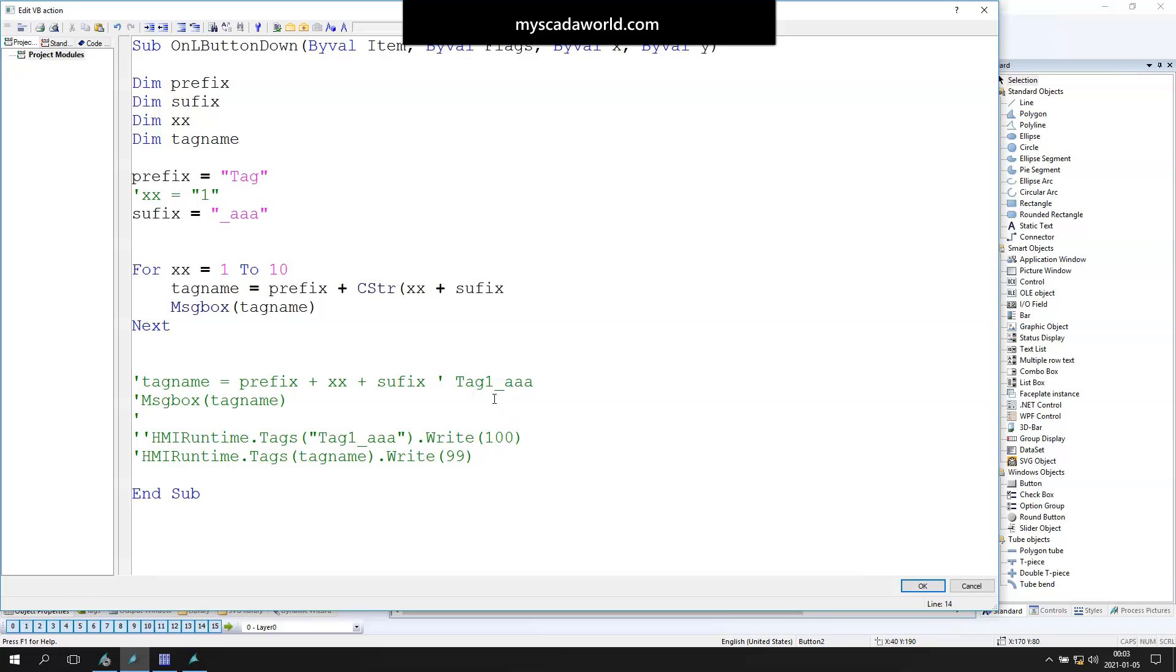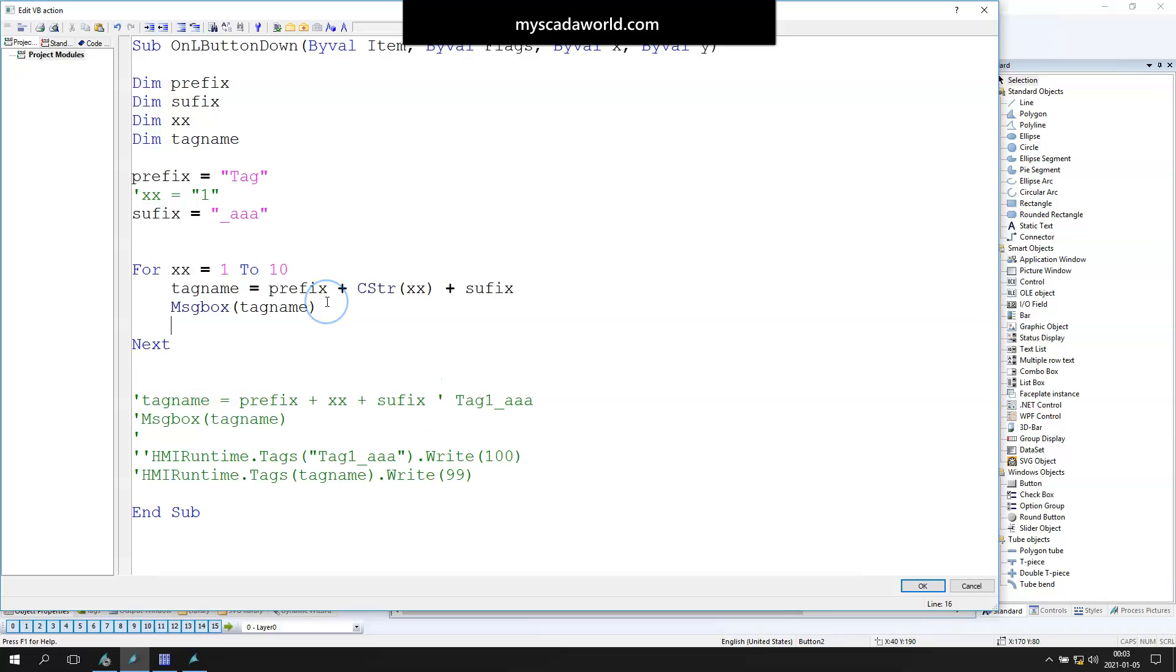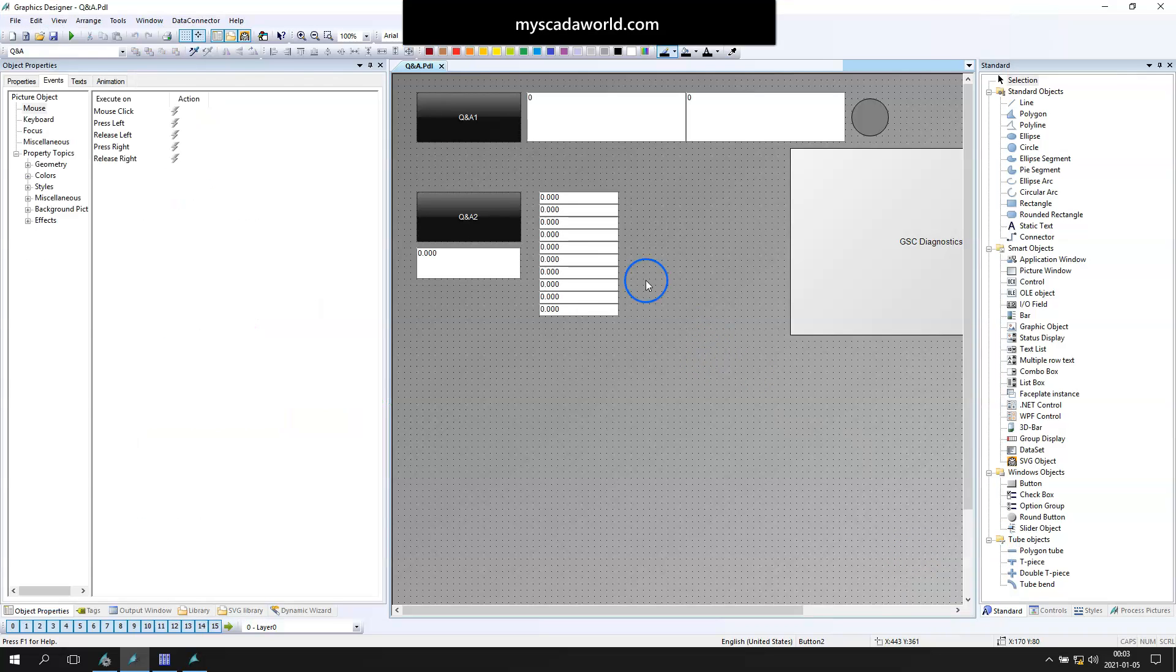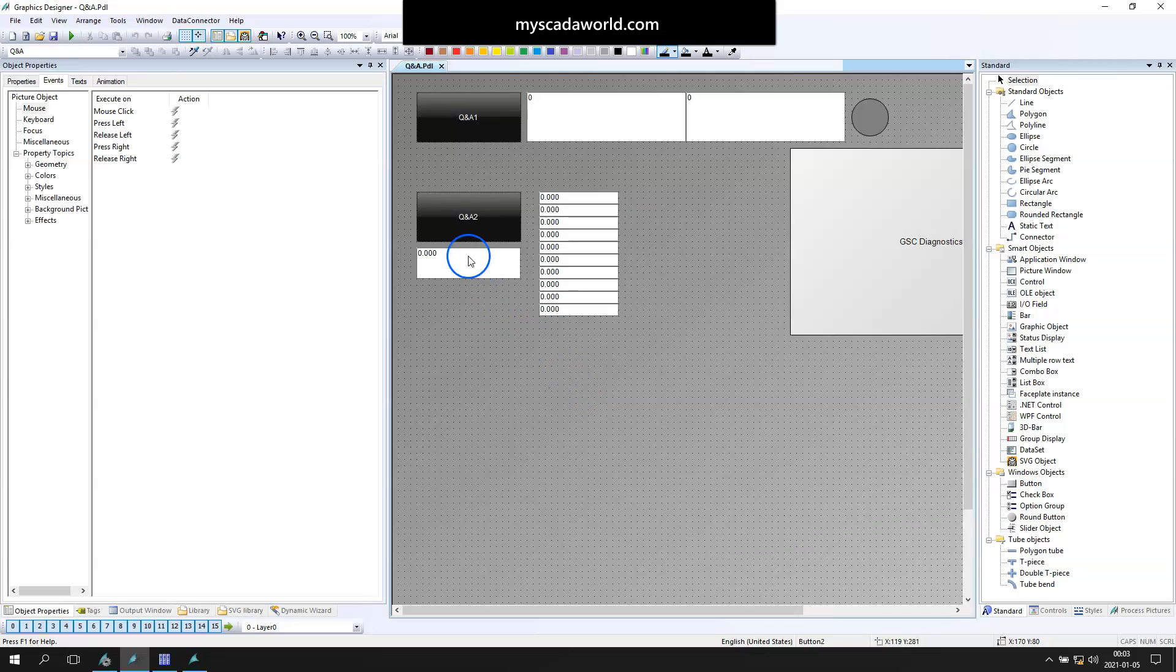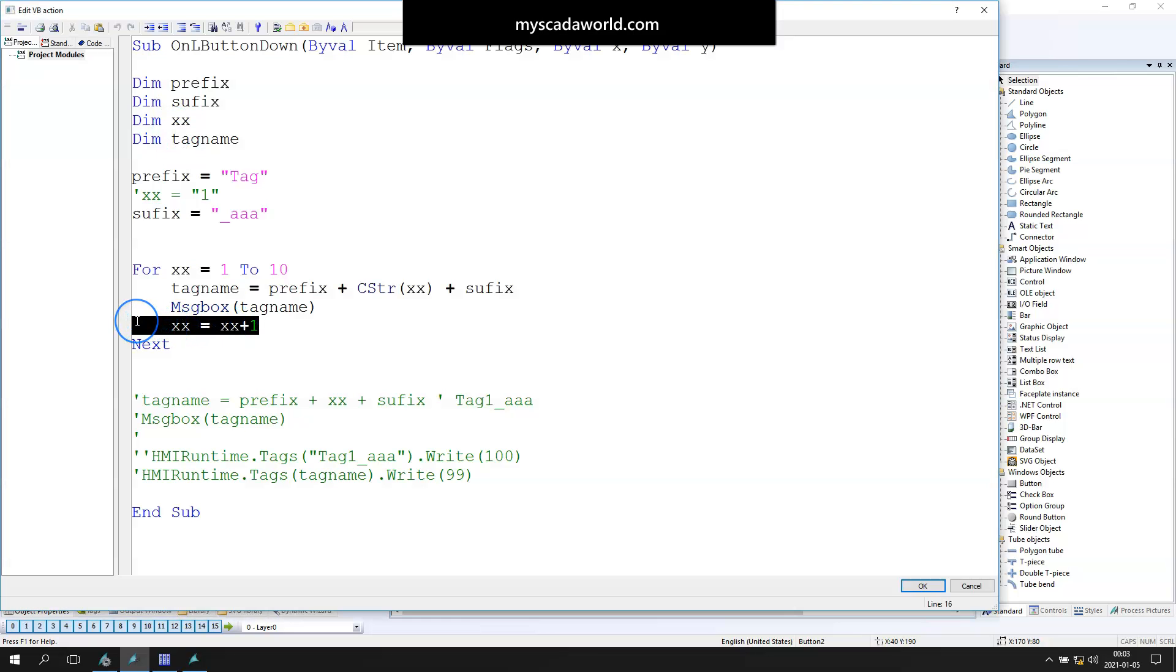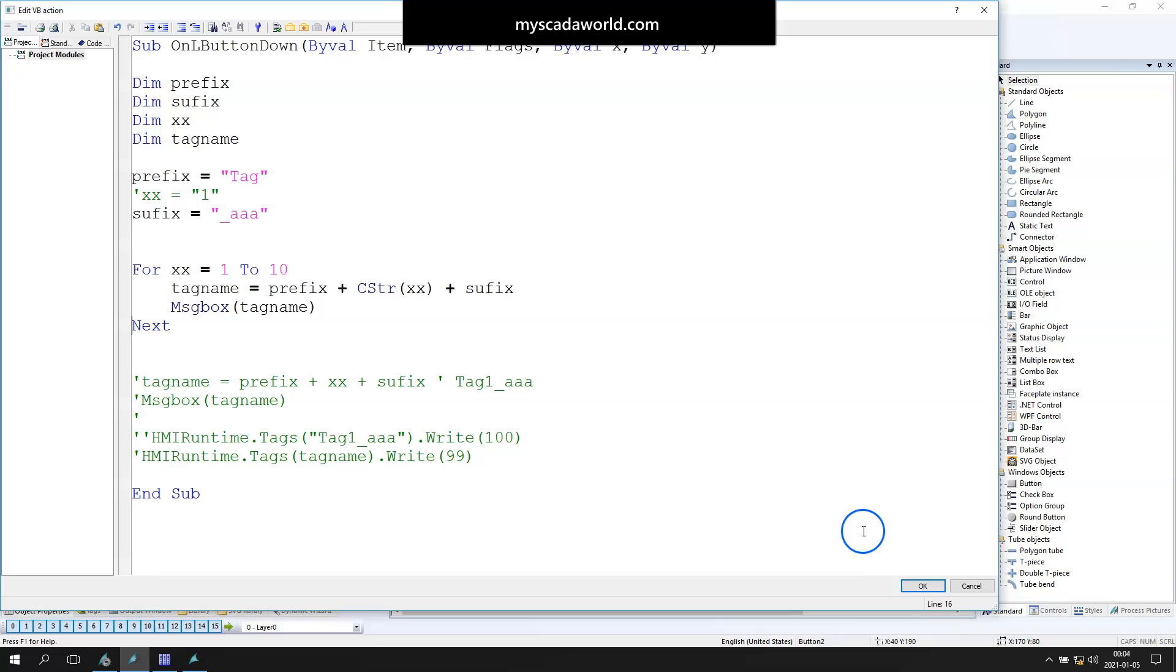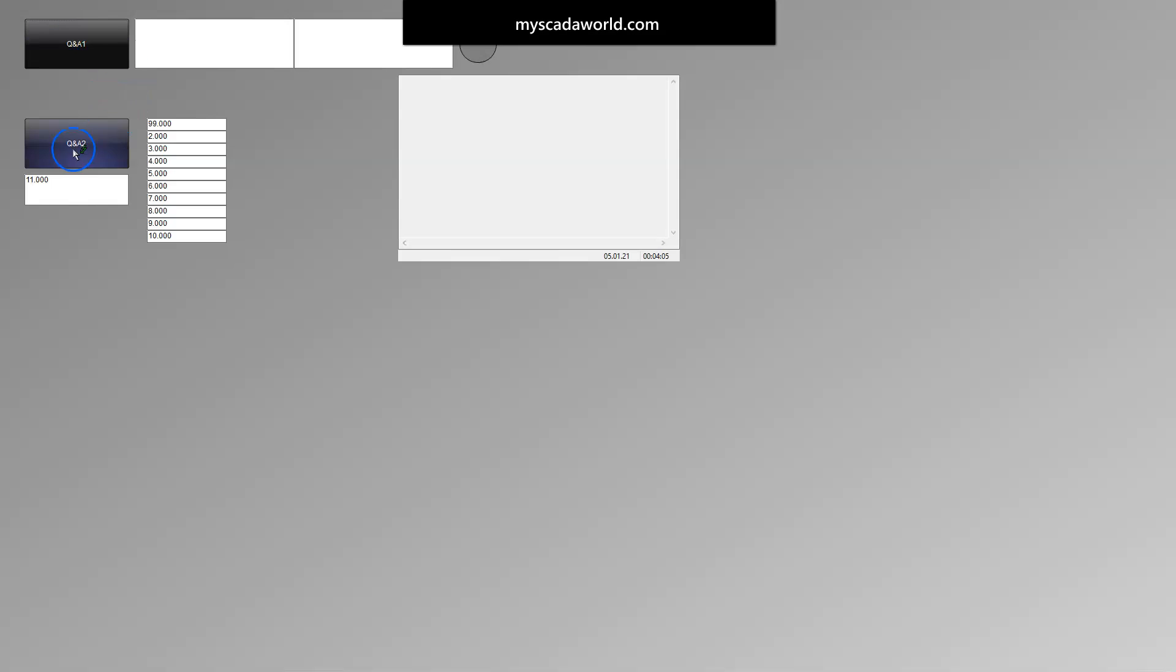CStr is the function to convert data from decimal to string, because our tag name is made with three different strings: prefix, x, and suffix. After this we have tag1aa, tag3, because I did one mistake more. I put xx is xx plus 1. We don't need to use this. Our for function is incrementing the xx automatically.